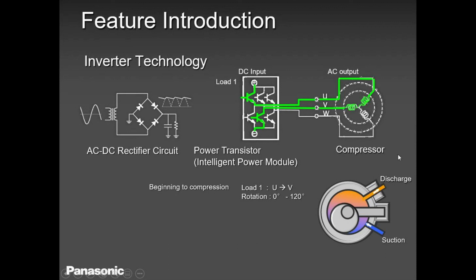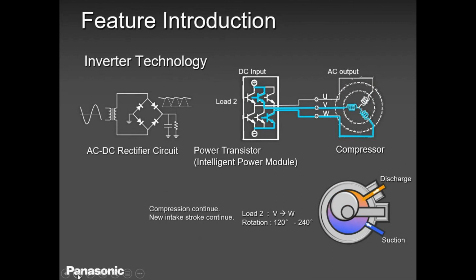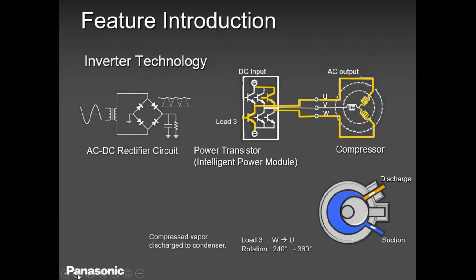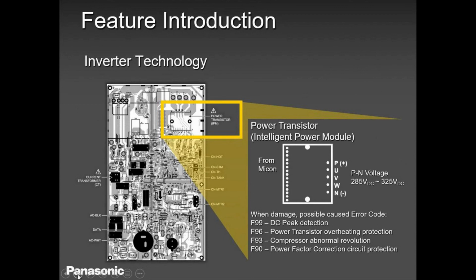So basically, at the outer unit, you will see just one board. Okay, you will just see one control board, and it's a board that involves the AC/DC rectifier, the IPM, intelligent power module, and your compressor. So what this AC/DC and the power transistor does is receive AC voltage, convert it to DC, and then again to AC voltage into 1, 2, and 3, UVW, 3-phase. Okay, that's where your compressor gets the voltage, and that's where the compressor is being regulated. So when the compressor is running at a lower frequency, I can rest assured that the voltage is lower, probably around 50, 60 volts between UV, VW, WU, or WV.